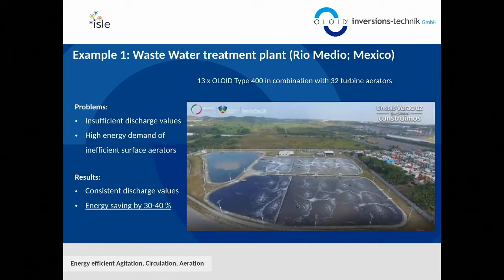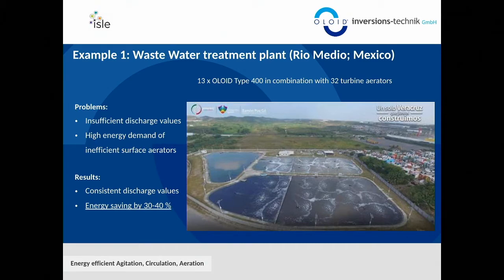Now some examples. In wastewater treatment plants, this is one of our biggest installations, in Mexico. Together with our partner and the engineering group, we redesigned a complete pond treatment plant that had a lot of odor problems close to the city — the plant was not running well. We implemented turbine aerators from our partners, plus our Oloid for oxygen distribution, plus disinfection at the end. The result, now running for three years: no more odor, better discharge values, and 30 to 40% less energy input than before.